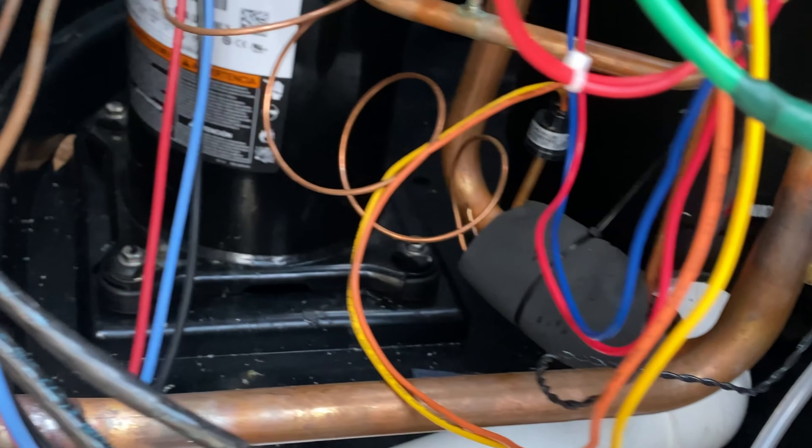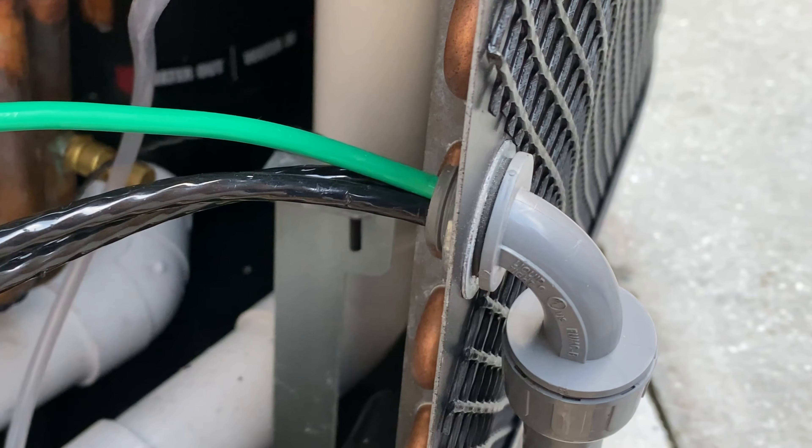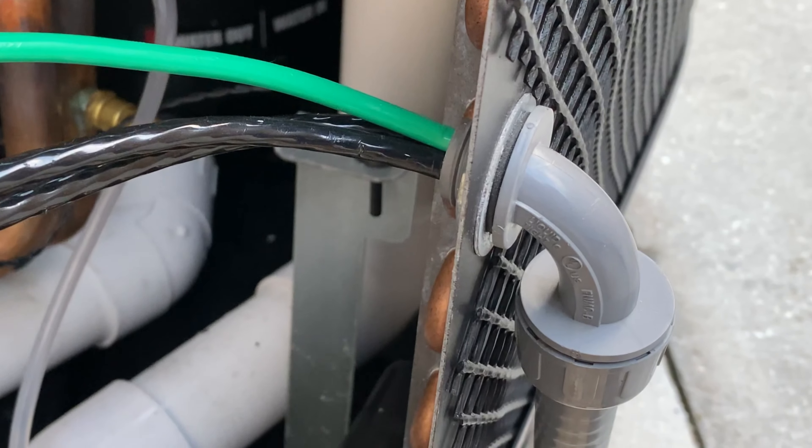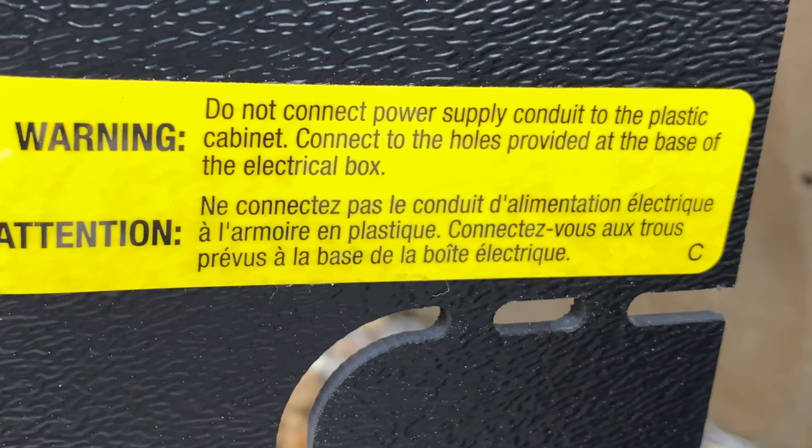All this electrical wire is live wire that's exposed to the elements. Definitely make sure you don't install a connector there. In fact, even on the door it says right here: do not connect power supply conduit to the plastic cabinet — which is exactly what that is.